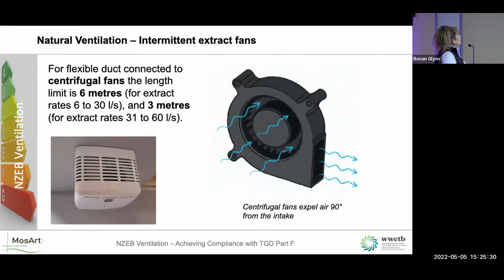So for that one, for the flexible ducting on a centrifugal fan, you're allowed to have 6 meters of ducting for small rates and then 3 metres of ducting for larger rates, so anywhere between 31 and 60 litres per second.